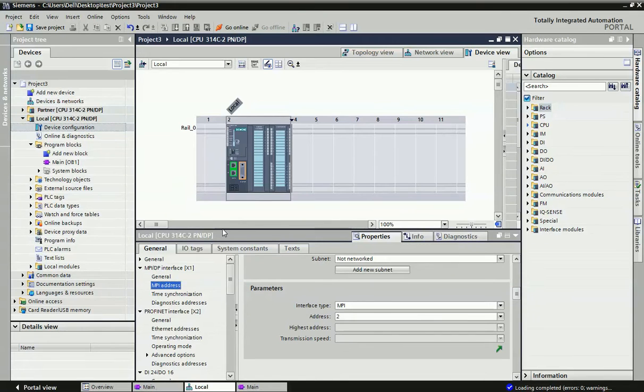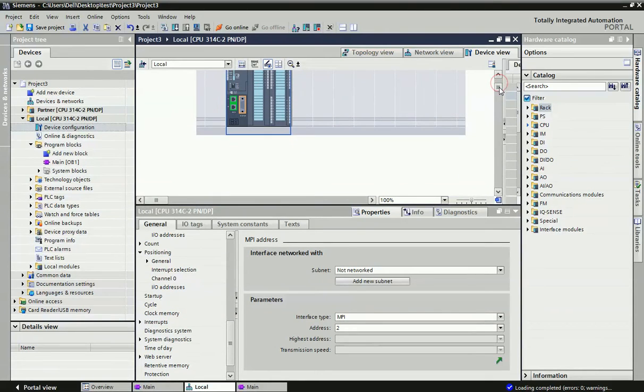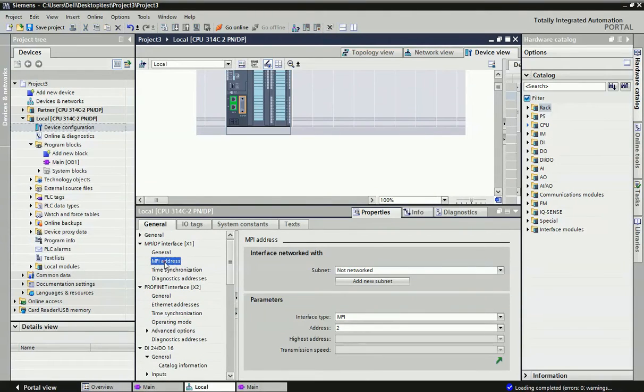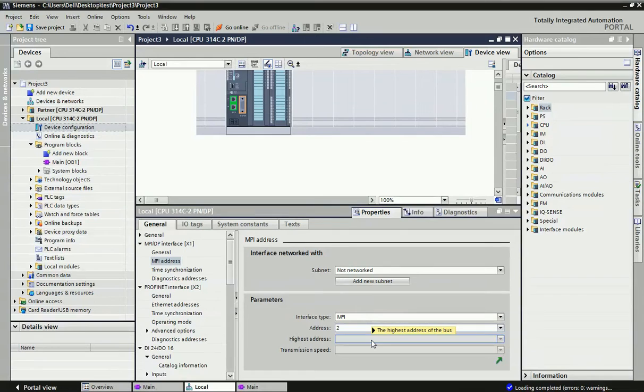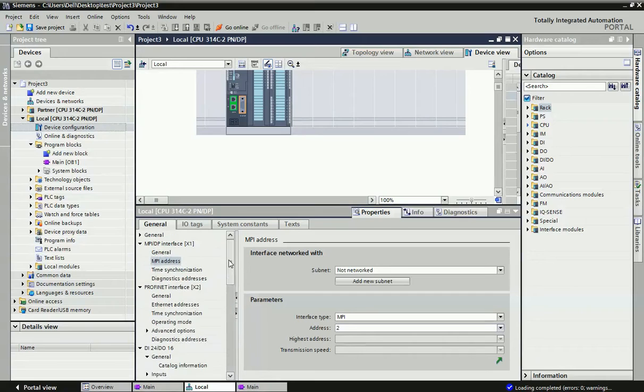In the PLC device view we will set the MPI address. From the properties we get the MPI address option, where we set the interface type to MPI and assign an address. We will also enable clock memory in both PLCs for data communication synchronization.